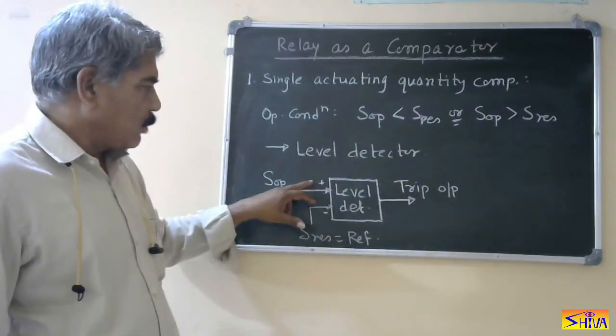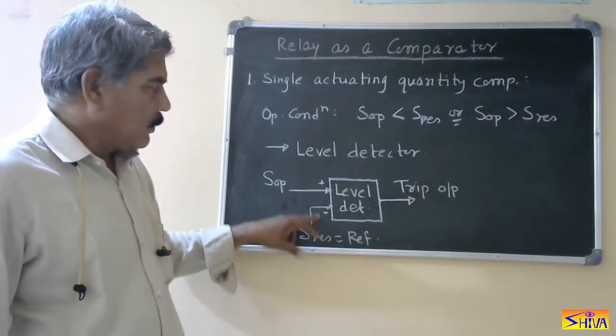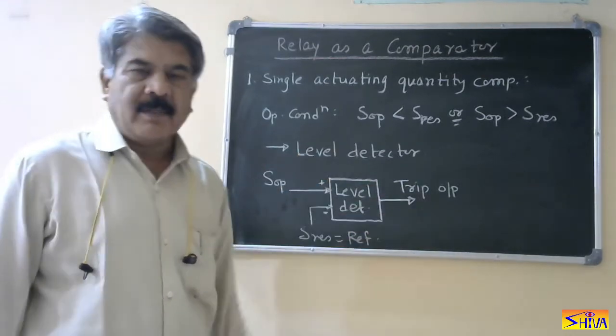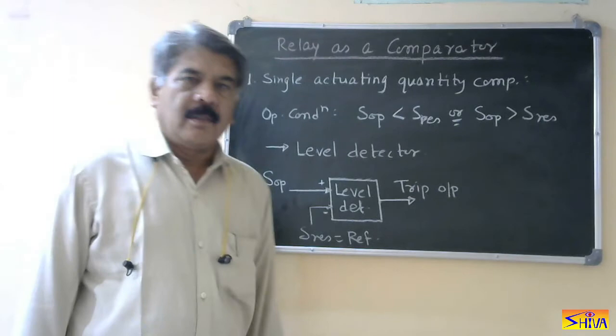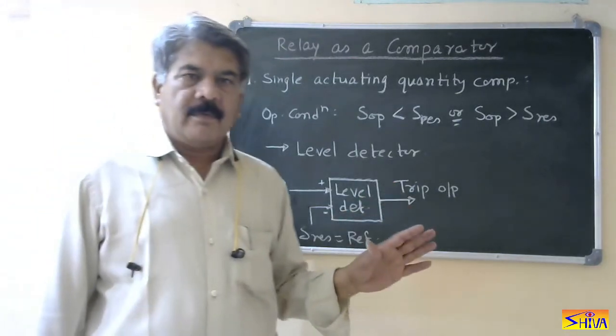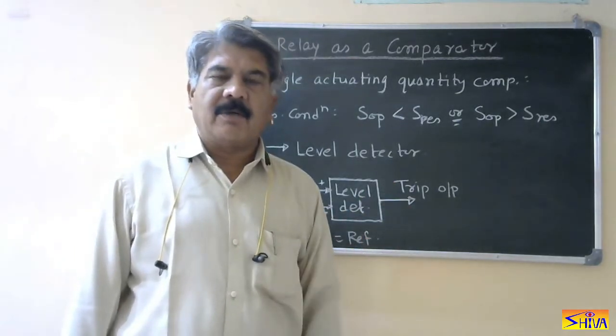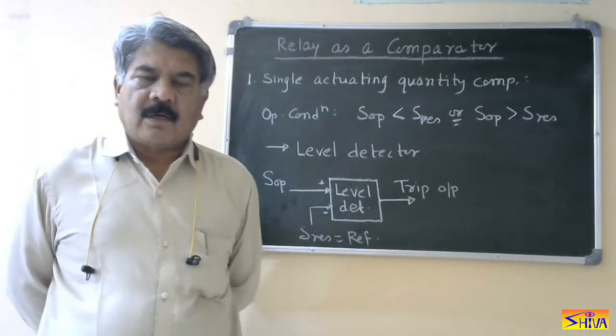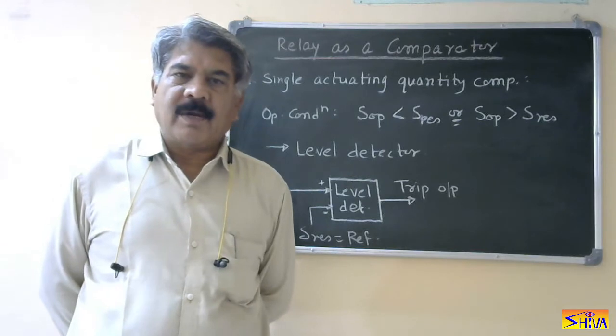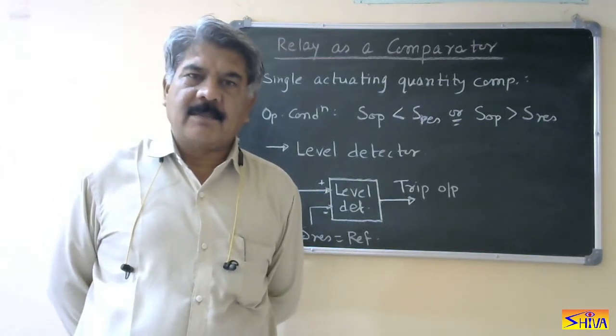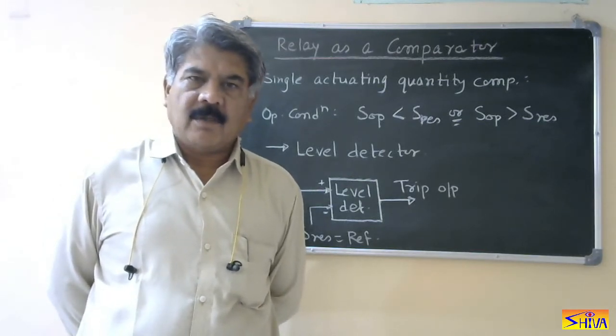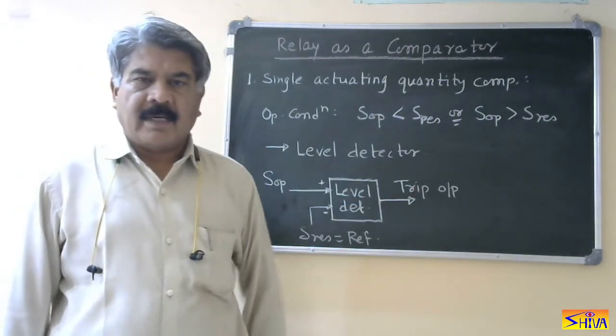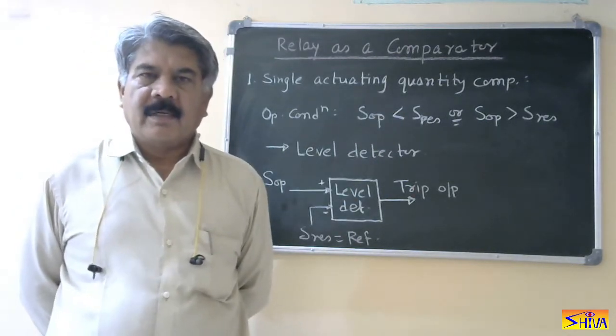For the undervoltage condition, when the operating quantity becomes less than the restoring quantity, we get the trip output. The advantage of this single actuating quantity comparator is that it is simple and cheap. The drawback is it does not provide the directional sense — that is the biggest drawback of this single actuating quantity comparator. It does not provide the directional feature.